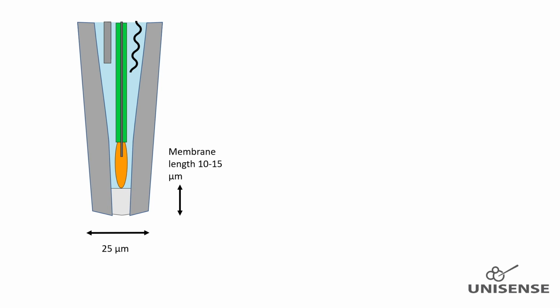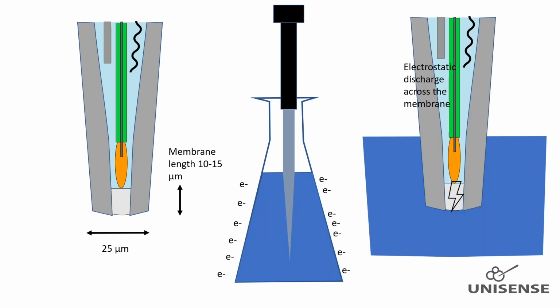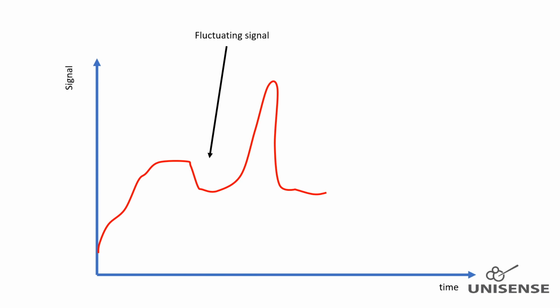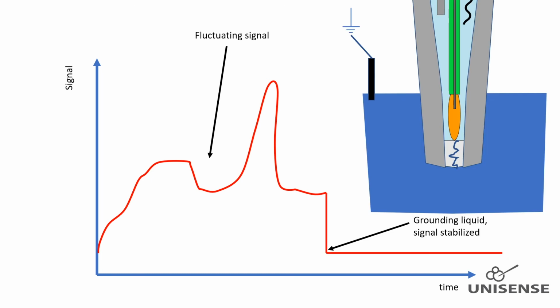Fast responding oxygen sensors have a very short membrane which can be vulnerable to electrostatic discharges. A charged person who touches, for example, a beaker in which the sensor tip is placed can induce a potential difference of thousands of volts across the membrane and potentially induce a discharge which destroys the membrane. To be sure that this does not happen, a grounding wire should be connected to the liquid or setup in which the sensor tip is placed, and to the ground socket of the Unisense amplifier. A sensor with a damaged tip membrane will have a very unstable signal, strongly affected by electrical noise. By grounding the sample or experiment to the ground socket of the amplifier, the signal will stabilize. A damaged membrane cannot be repaired.